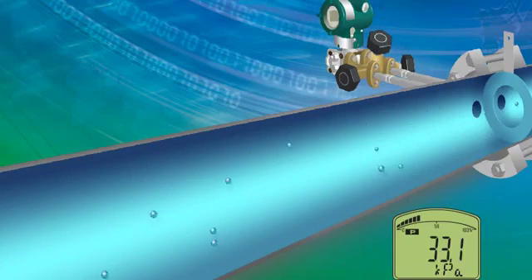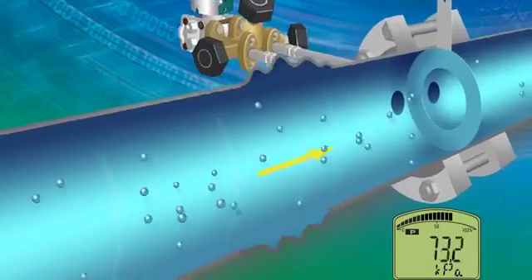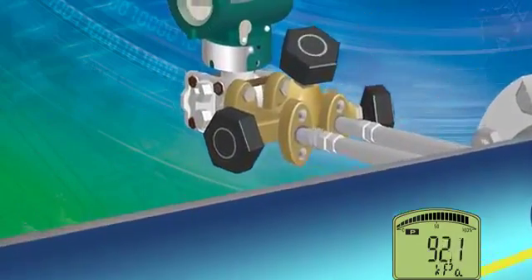Overpressure can cause a pressure transmitter to fail or impair its performance. This effect happens when excessive differential pressure is applied to the device, which is greater than its measuring range.